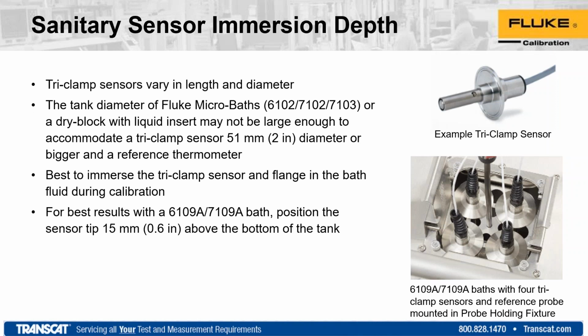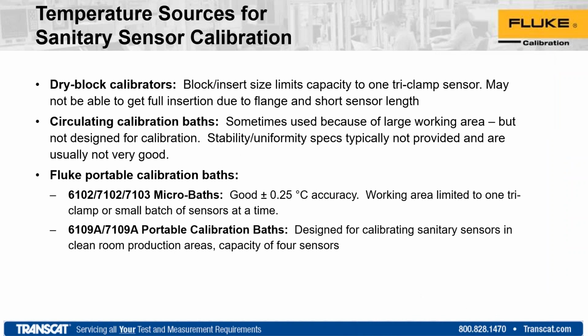Like with all sensors, the TriClamp sensors vary in lengths and diameter. We've got a few different baths that we've used in the industry over the years that work well, and people have used these as well as some of our standard baths. But with this design, we went at the market of improving your throughput, having the ability to test more than one at a time, which is the case with some of our smaller micro baths, and to provide some additional flexibility with immersion depth. We'll touch on that as we go through this. I've got some slides on some of the features of the bath itself, to get the best results in the field from the testing process.